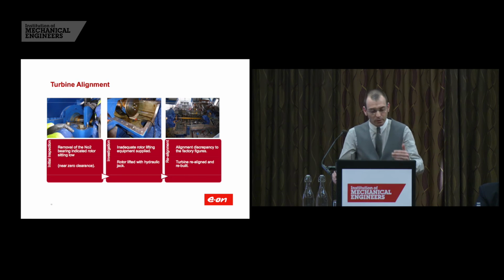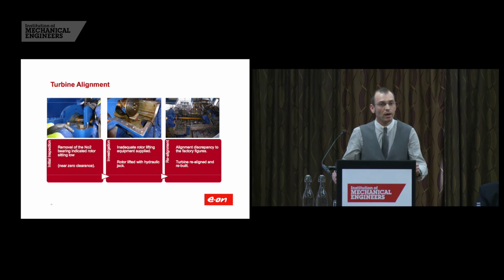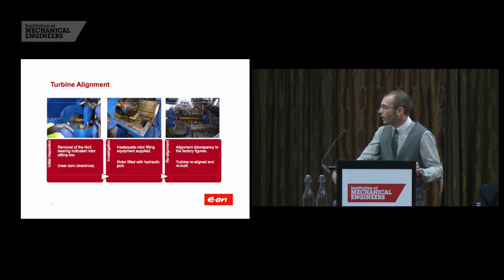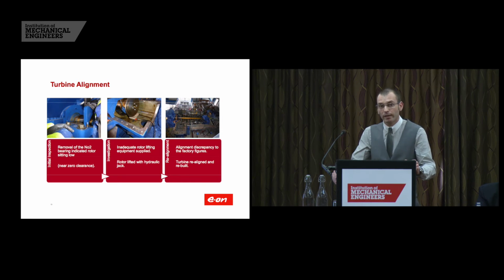However, because there was an unknown quantity, that we didn't know whether there was any damage within the machine, it was decided that we'd have an unforced outage and open the steam turbine. On first removal of the bearings and installation of the shaft raising gear, it was found that the shaft would not raise, and it was feared that it was wedged, fueling belief that there was actually damage internally to the machine. After discussions with the site team, it was elected to put a hydraulic ram under the shaft and slowly lift the shaft to see if it would move.